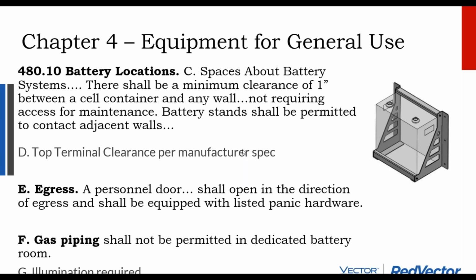And all of your working clearance requirements apply that you see in the earlier sections of code, such as vertical spacing and clearance behind you. Basically, in a dedicated battery room, if your batteries are in a room, you need to be able to fully stand up in that room. You're looking at 6.5 feet of vertical clearance, and anywhere from 3 to 4 feet behind you before you get to the next wall. So these battery rooms have to be rather sizable and professional. If you don't have enough space for a battery room, build a battery box instead. Don't build something that's halfway a room. Don't build a battery box that is so large that it's really a room. If you're really building a room that you have to go inside to work on the battery with, then it needs to be a proper room.